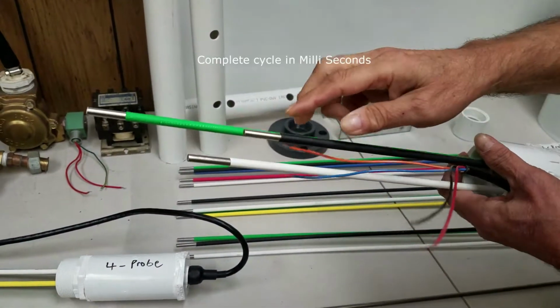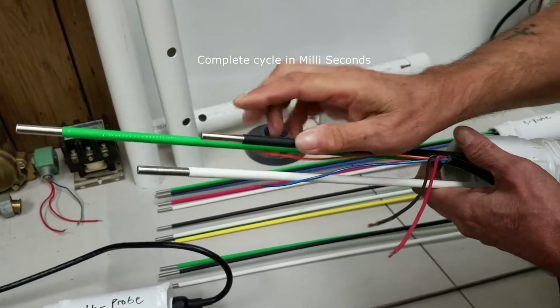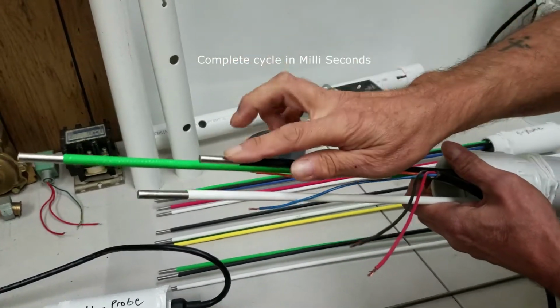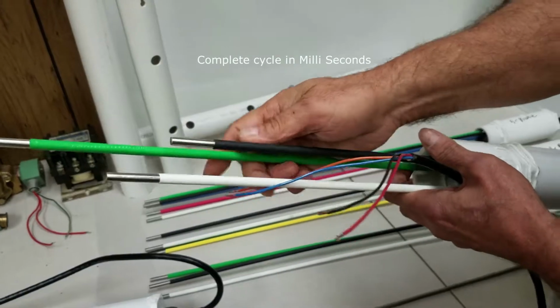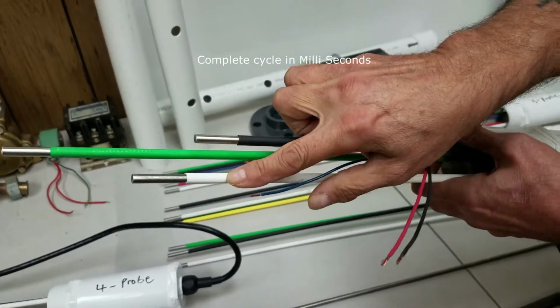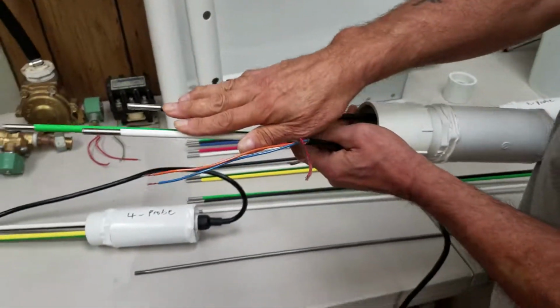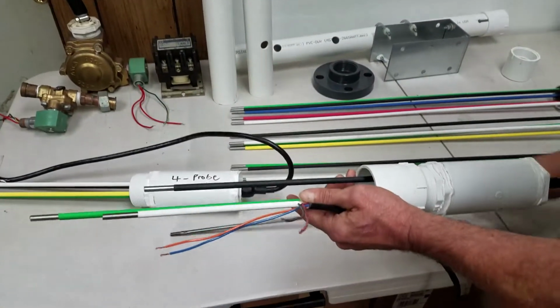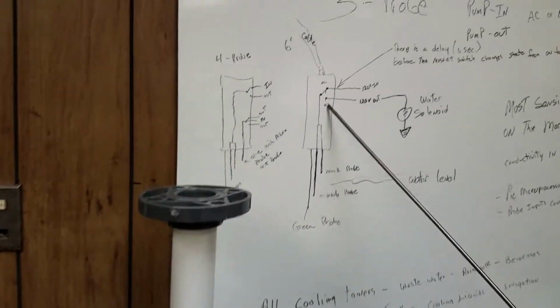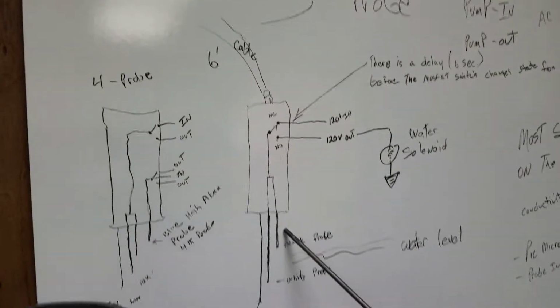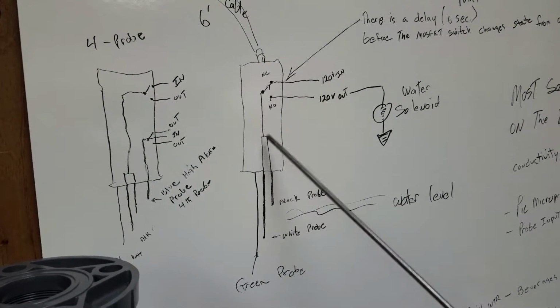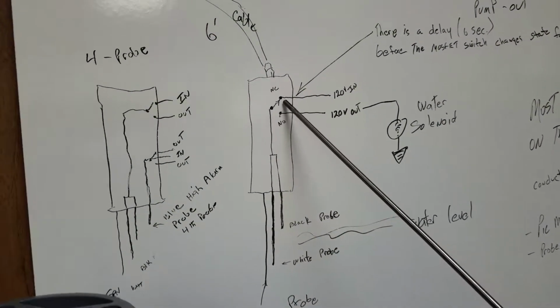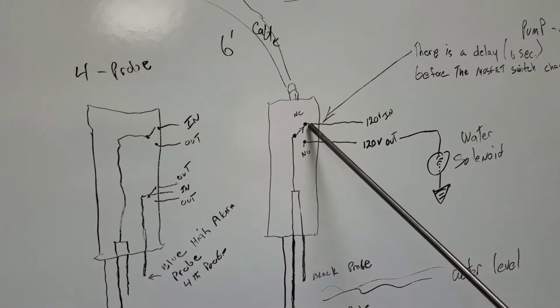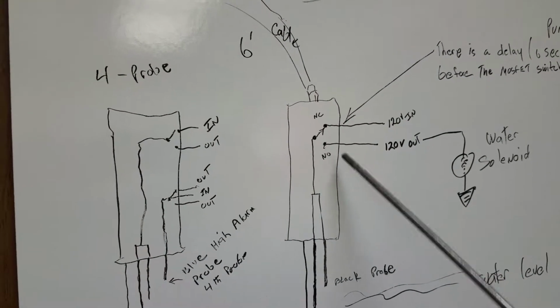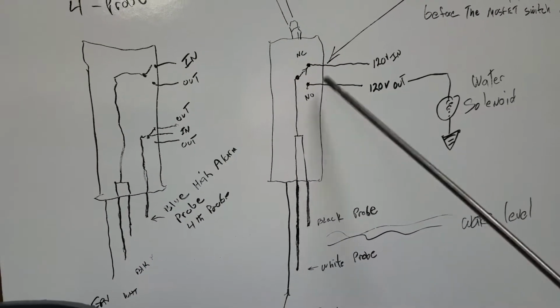The reference probe: we transmit on all the probes and receive on one. And then we'll transmit on all the probes and receive on another. So 2 probes control 1 relay, one contact. 2 probes, your black and your white, control a single contact, which is either going to be closed or open, depending on whether it's in the water or not. Your inputs, your output. 2 probes control 1 contact.